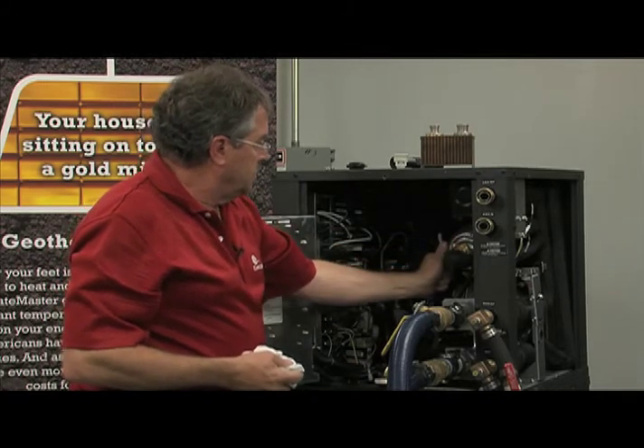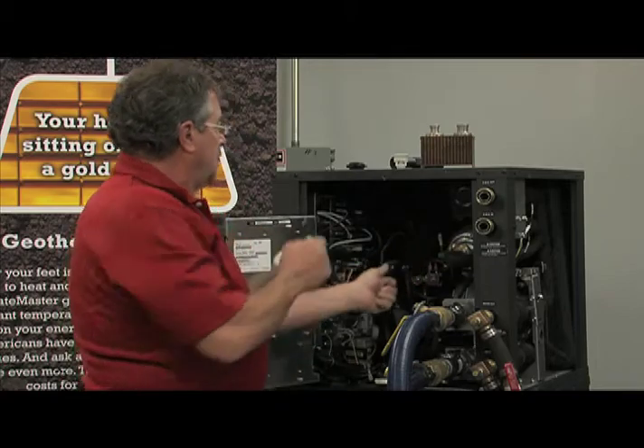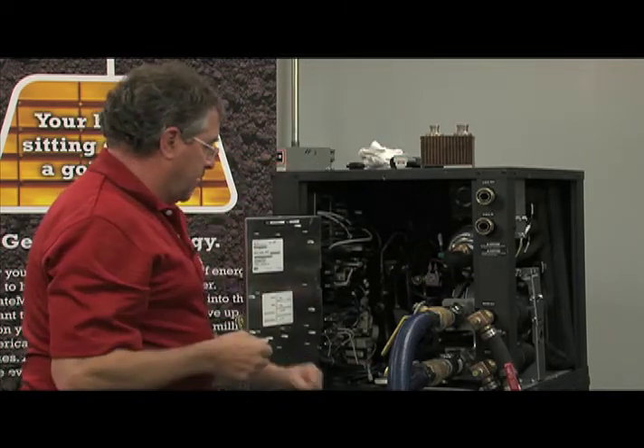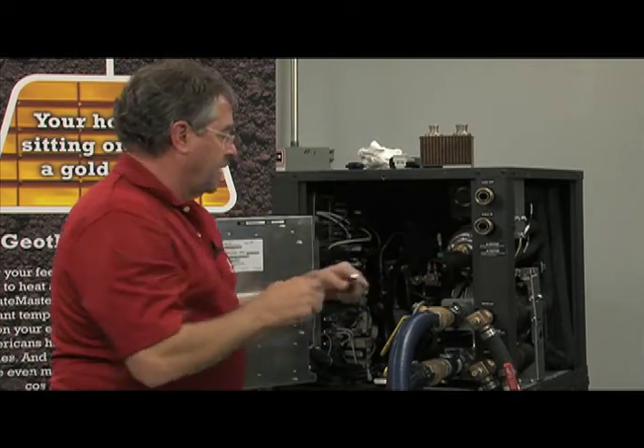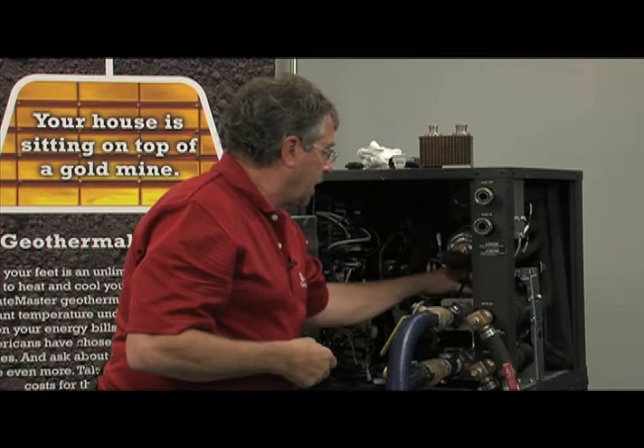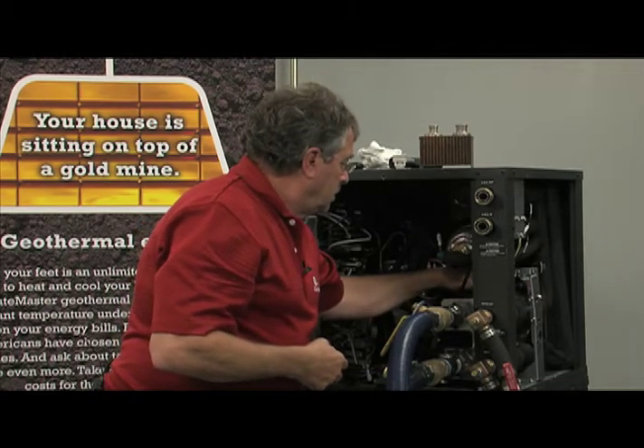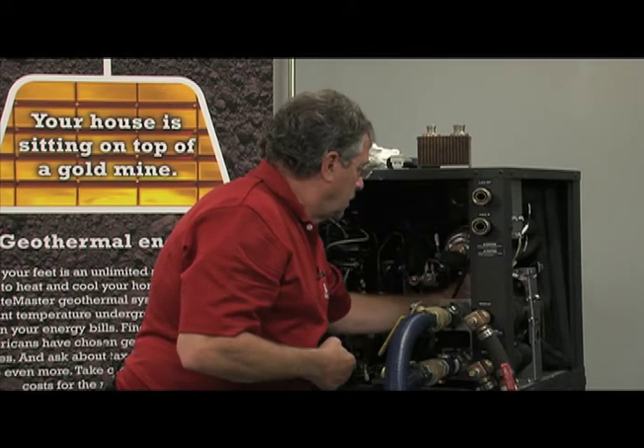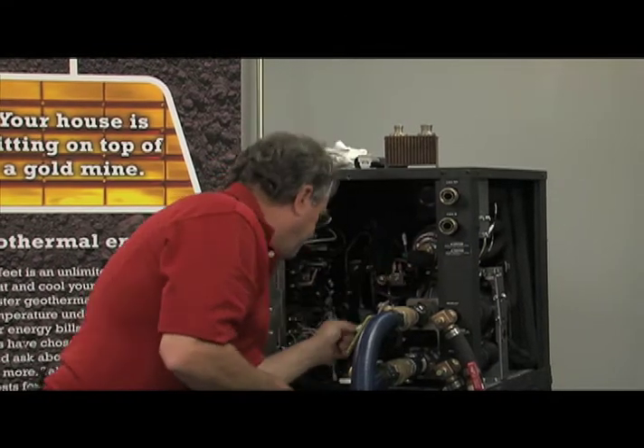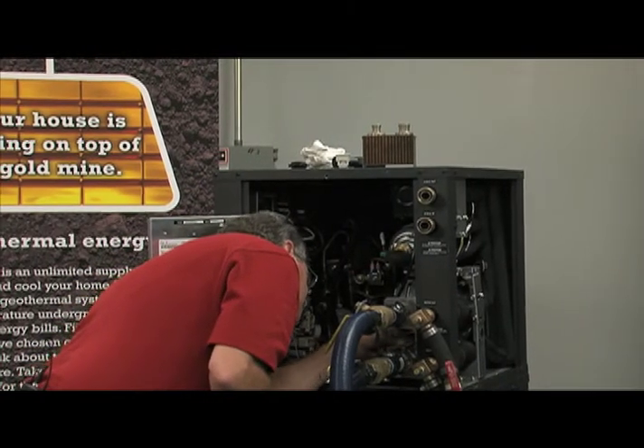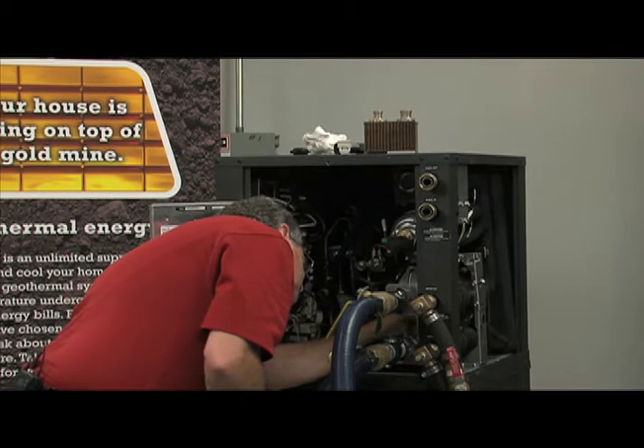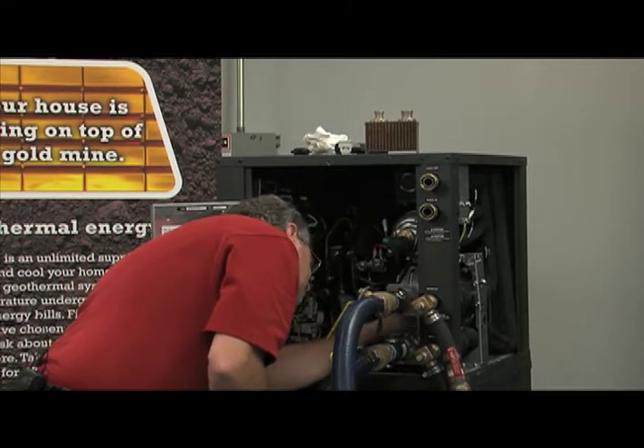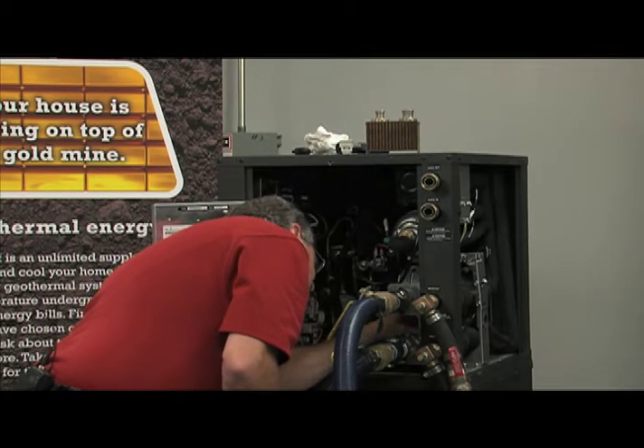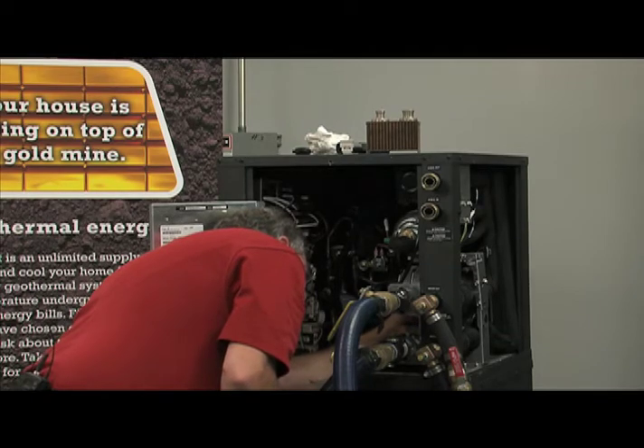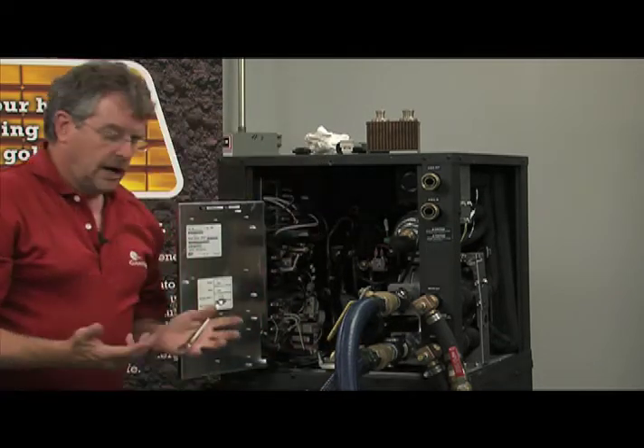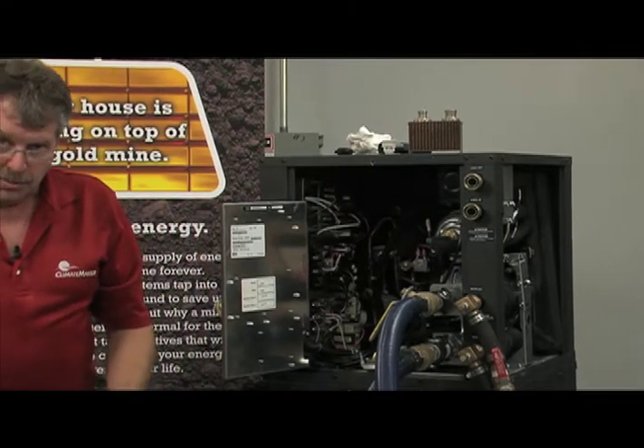Again, my pump is still operating, so I can go ahead and open that valve, which puts a volume of fluid inside that expansion tank, and now I can go ahead and put my flush valves for my vFlow into the service mode, which isolates our flush hoses and makes it a closed system at that point. And now that's complete, we can go ahead and shut our pump off.